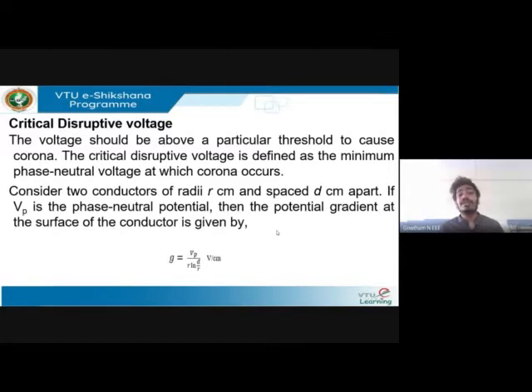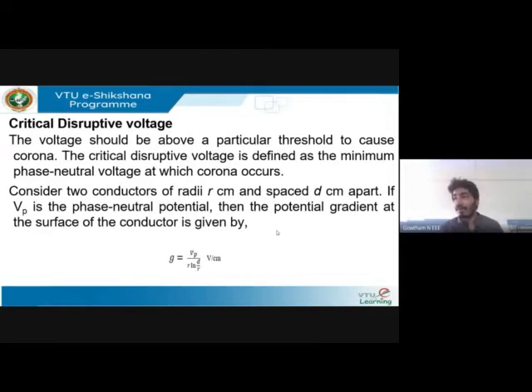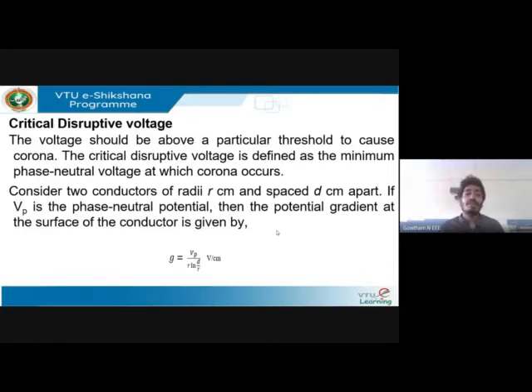The next objective is critical disruptive voltage. This is the voltage at which corona starts — around 30 kV. It is defined as the minimum phase-to-neutral voltage at which corona occurs. Below this threshold — say 25 kV or 10 kV — you don't have corona, but exactly at 30 kV, corona occurs. That is the minimum phase-neutral voltage at which corona occurs.